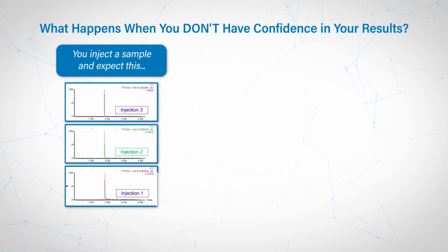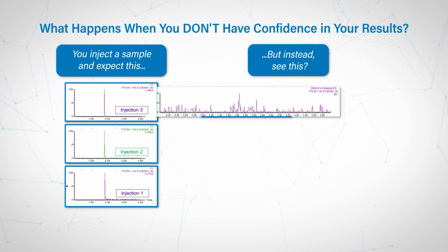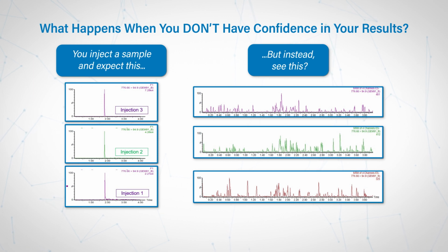I have, yeah. It's actually happened to me a couple times. What do you think's going on? Does it look something like this, where on the left-hand side you're seeing the peaks you're supposed to be seeing, injection 1, 2, and 3, but then he switched out the column and saw no signal at all? Yeah, that's exactly it. Like, where did that peak go?